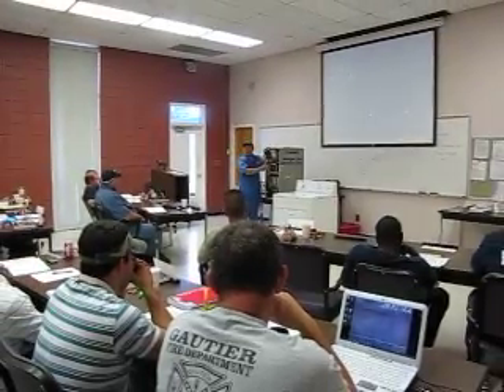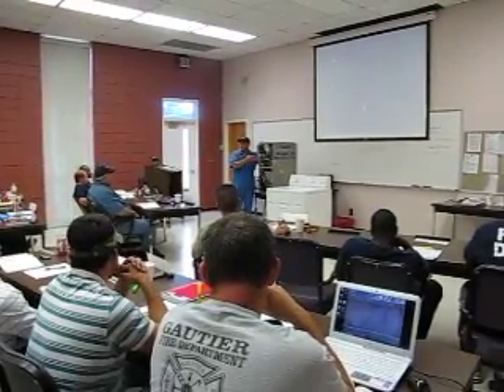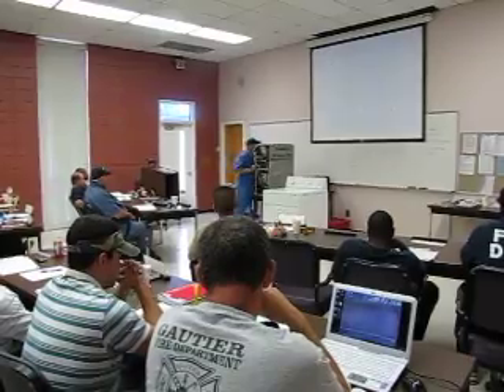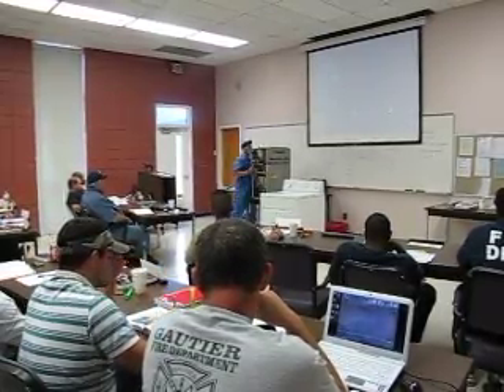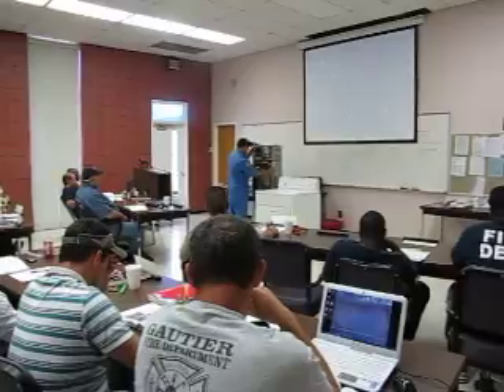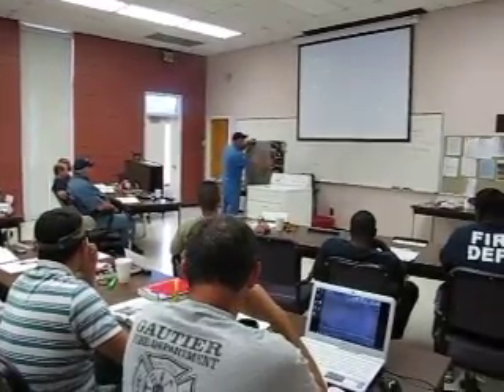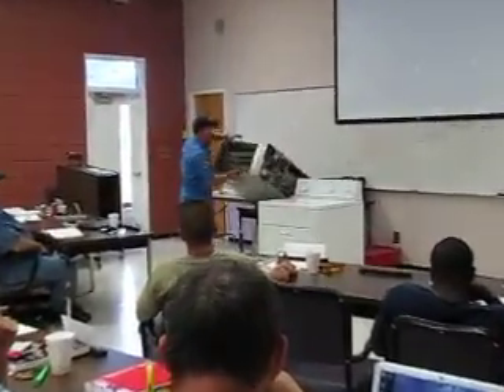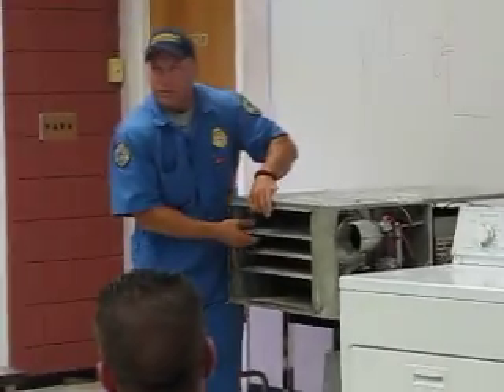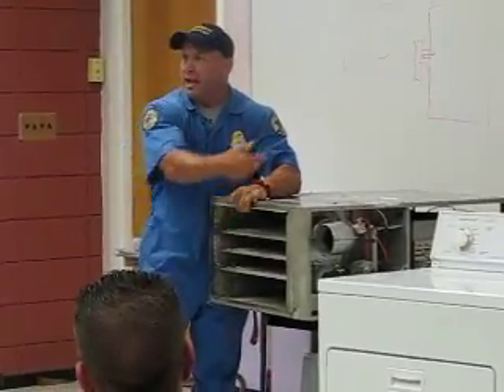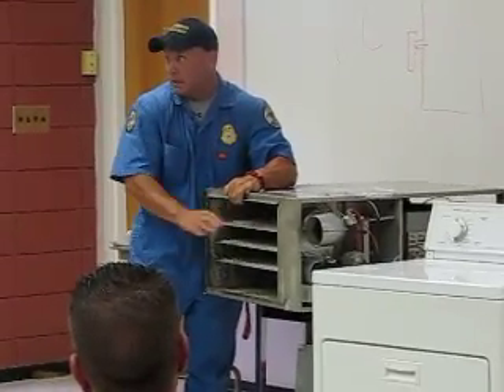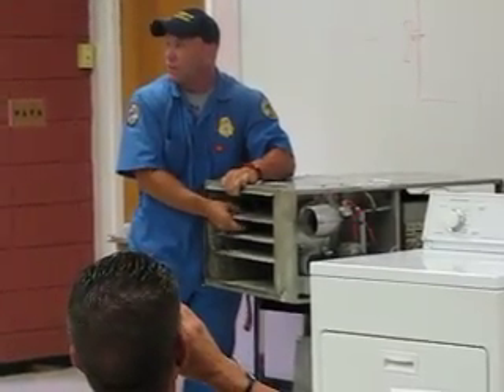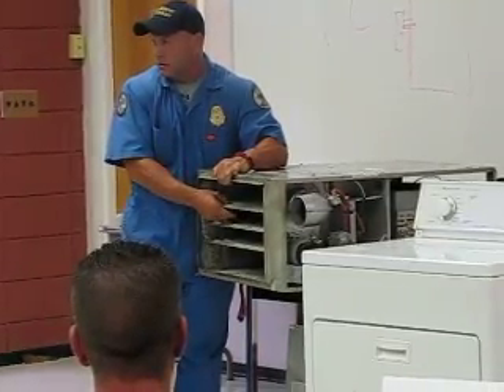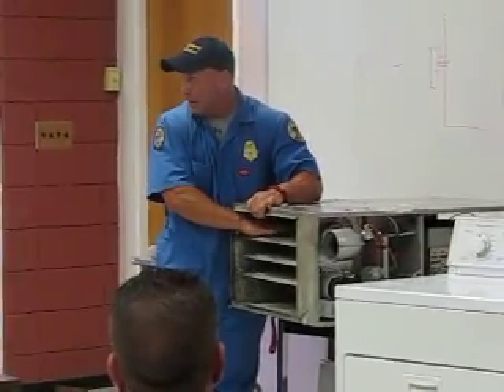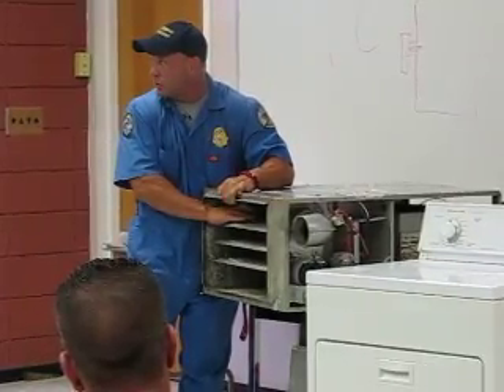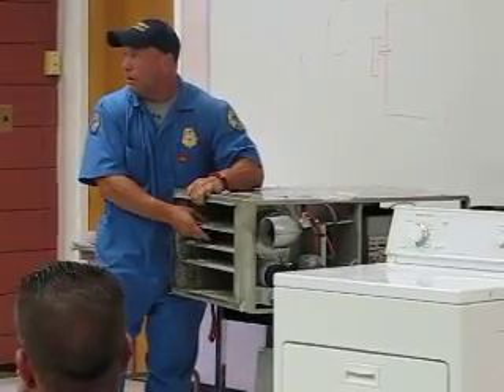And once the gas is lit, it blows the gas into the exchangers. Now the heat exchangers are probably the most important part to the fire investigator, because this is exactly probably what causes the most problems. This is your heat exchanger. So the gas is now forced up as it's basically combusted. The combusted gas is forced up into these heat exchangers.